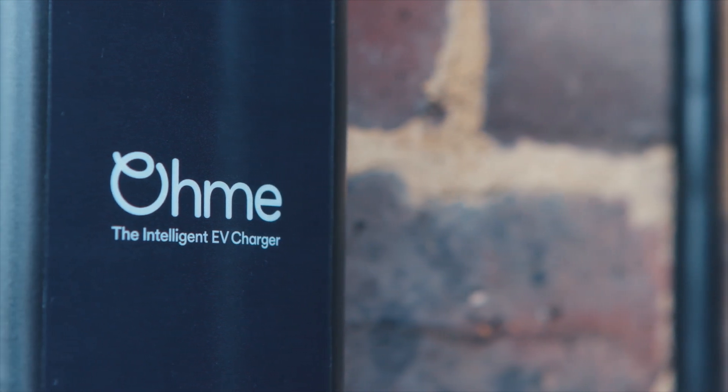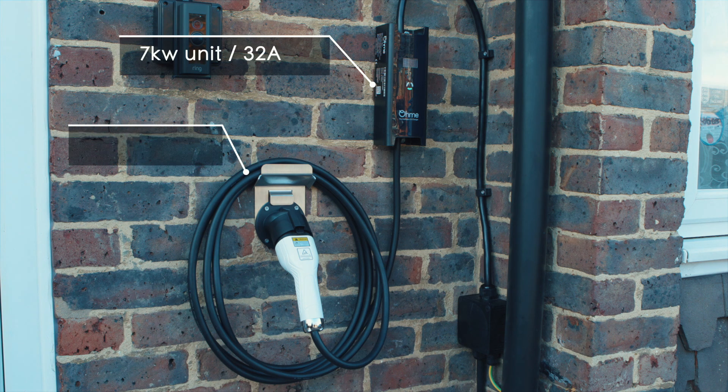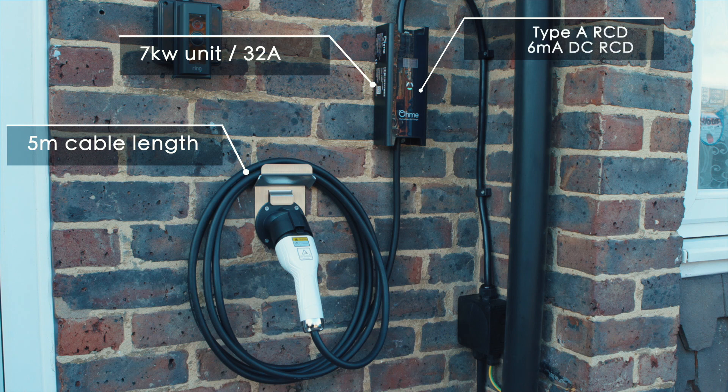The Ohme charger is an OLEV approved smart charger. It charges at 7 kilowatts or 32 amps and has a 5 metre lead length. Inside we have the Type A RCD and also the 6 milliamp DC detection, and it's available in both Type 1 and Type 2 connectors.